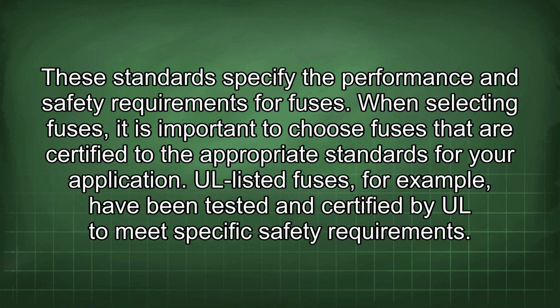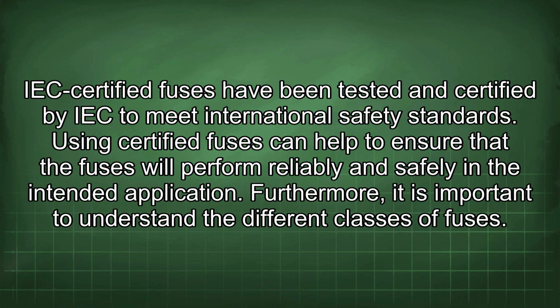UL-listed fuses, for example, have been tested and certified by UL to meet specific safety requirements. IEC-certified fuses have been tested and certified by IEC to meet international safety standards. Using certified fuses can help to ensure that the fuses will perform reliably and safely in the intended application. Furthermore, it is important to understand the different classes of fuses.